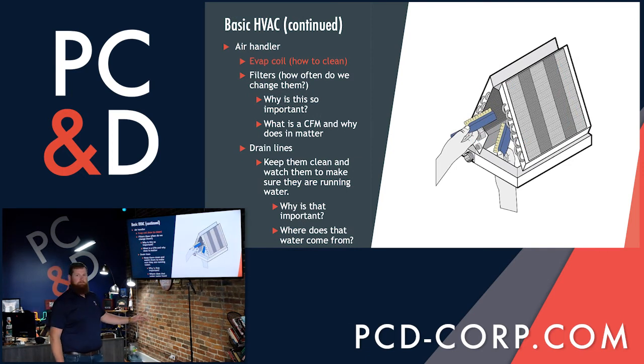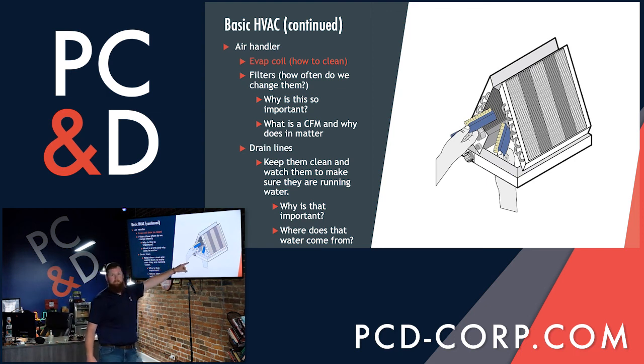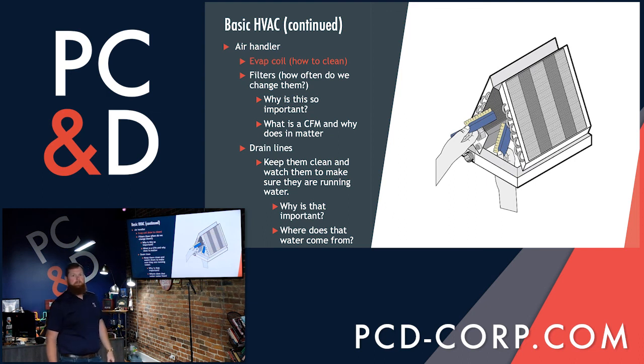Inside the unit of the HVAC system located indoors is known as the A coil. As you can simply see, it looks like an A, and it is right above the fan motor, and the freon that's being circulated through the system actually goes through the A coil. Right below this A coil, which would be that right hand, is typically where your filter would be located, and what it does is prevent any debris from reaching the underside of it.